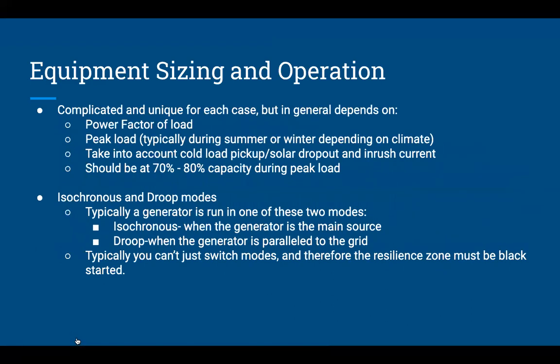Equipment sizing and operation is very important and unique in each case. In general, it depends on the type of load, the power factor, and peak loads during summer and winter, and the generation capacity should be 20 to 30% above the peak load. For generators, it's also important to consider isochronous and droop mode operation. Since the switch between these two modes cannot be made seamless, we would have to start the resilient zone from a black start.